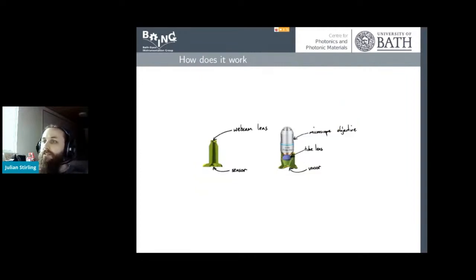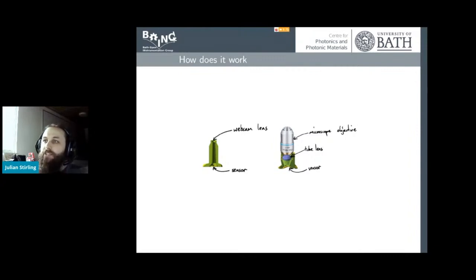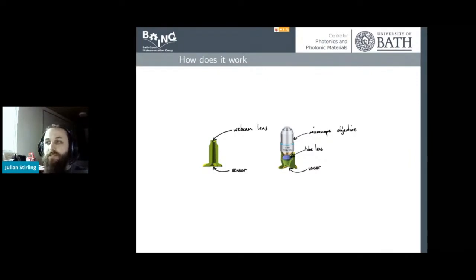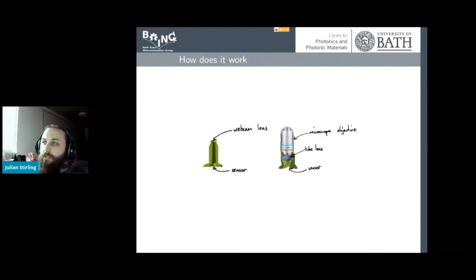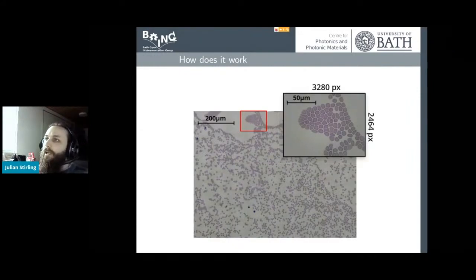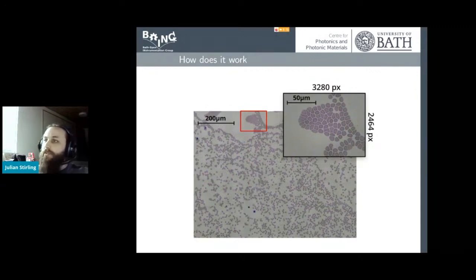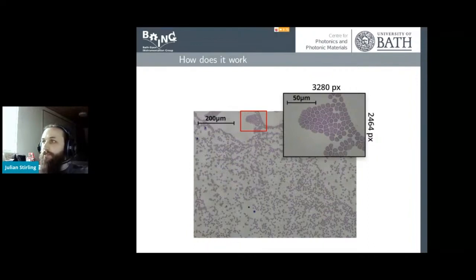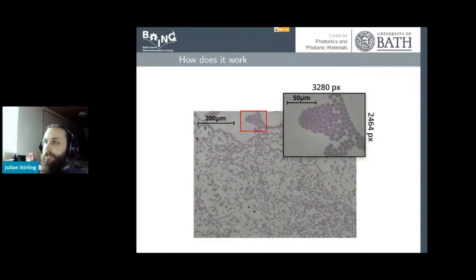We do need some optics, so we've got a camera sensor. You can build a low-cost version by taking a lens off a webcam, turning it around, and putting it a distance away from the sensor to get quite a good microscope — though not good enough for medical use. Or you can take a good microscope objective, bought for about $50 on Aliexpress, with another lens underneath and a sensor, and build a very good quality microscope. Here we have an image of red blood cells for malaria diagnosis. This is a stitched image of multiple 8-megapixel images; normally a technician would manually move around looking for parasites, but the automated microscope can move around and you can zoom in on different areas to look for parasites.